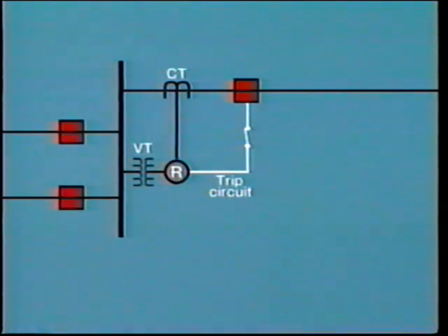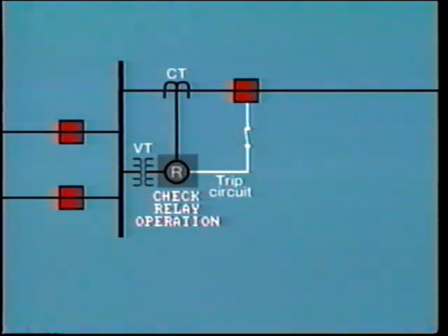In-service tests usually take two forms. One is to check the inputs to relays from CTs and VTs. This is to ensure that the sensing circuits are functioning correctly. Secondly, it is necessary to test the relays themselves for operation.